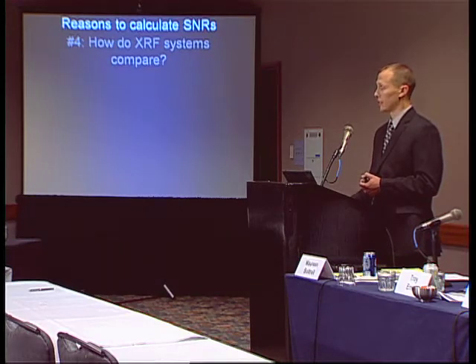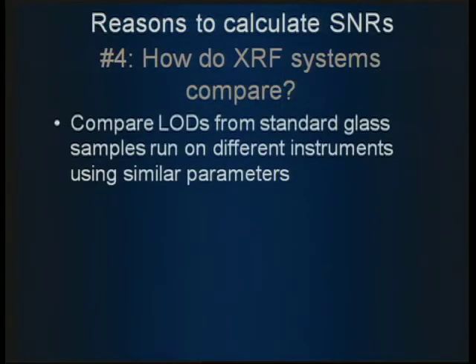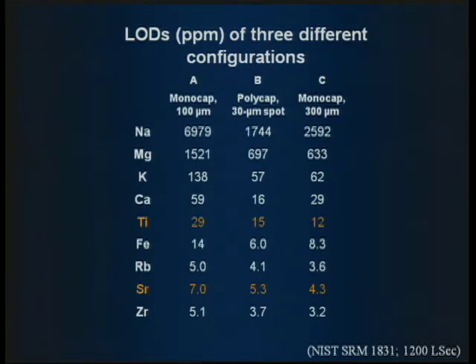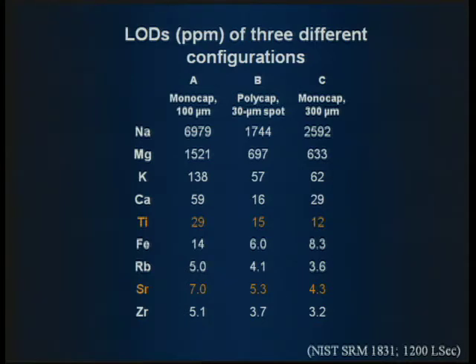Once you have the signal-to-noise ratios, you can compare XRF systems — for purchasing decisions, troubleshooting, or improving your methodology. You run the standard glass samples, calculate your LODs, and compare them from one system to another. This slide shows a comparison of three different configurations collecting from SRM 1831 for 1200 live seconds: a 100 micron mono-cap, a poly-cap, and a 300 micron mono-cap. They all follow the same general trend of LODs going from thousands down to single digits, but they differ from one system to another. Titanium and strontium are highlighted for comparison on the actual spectra.